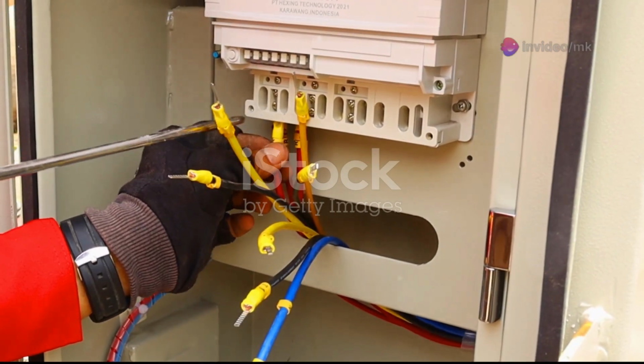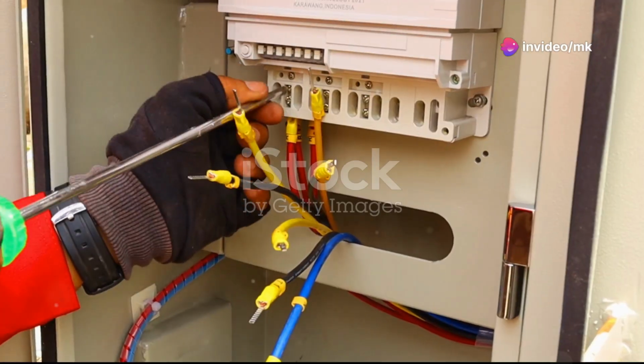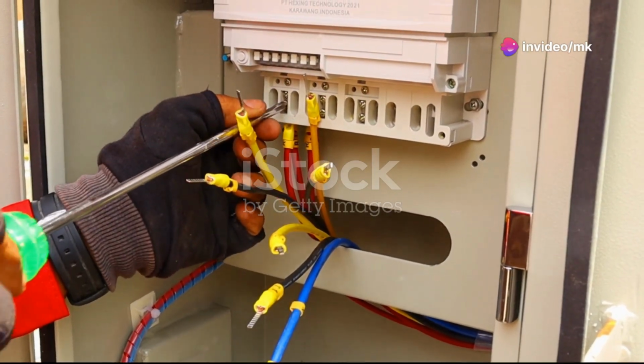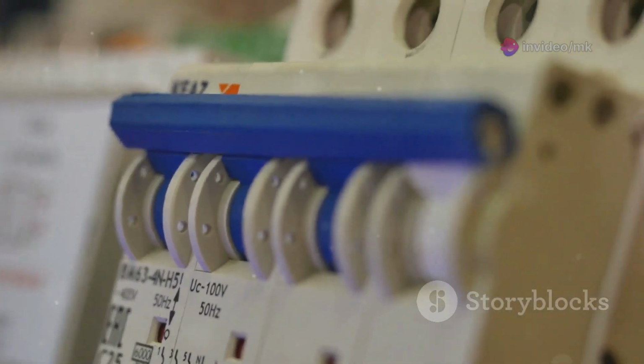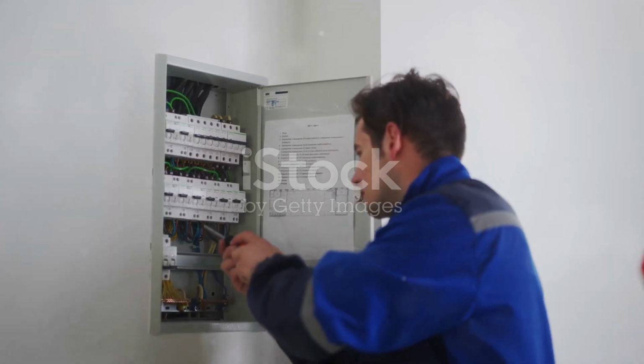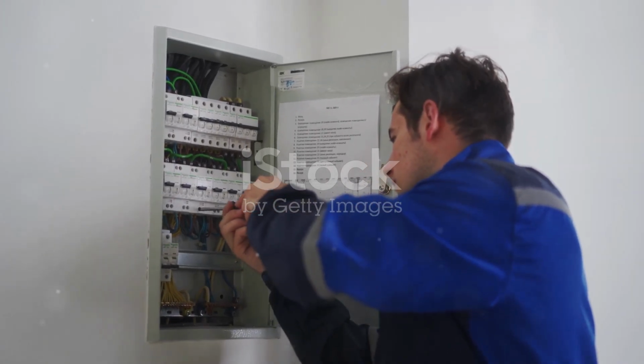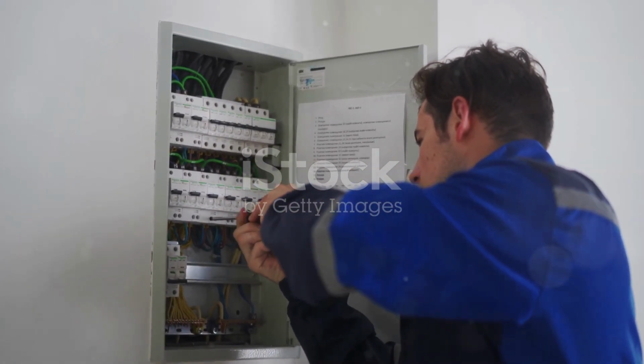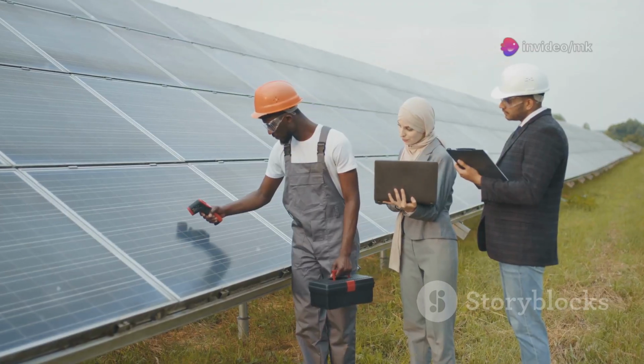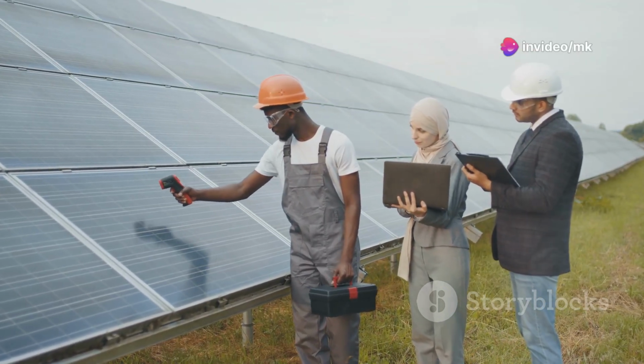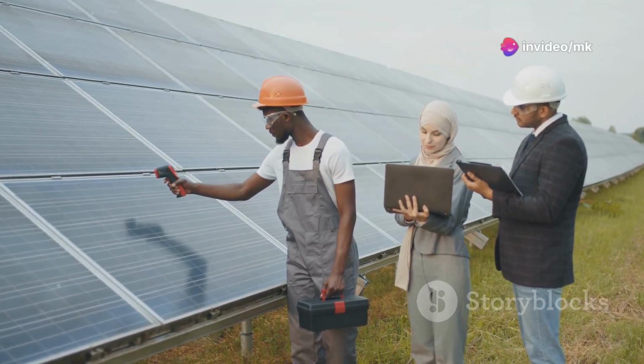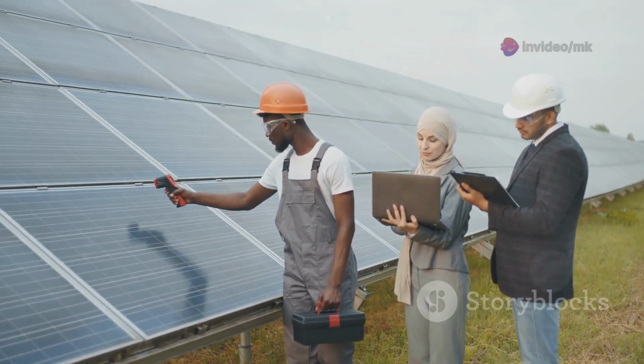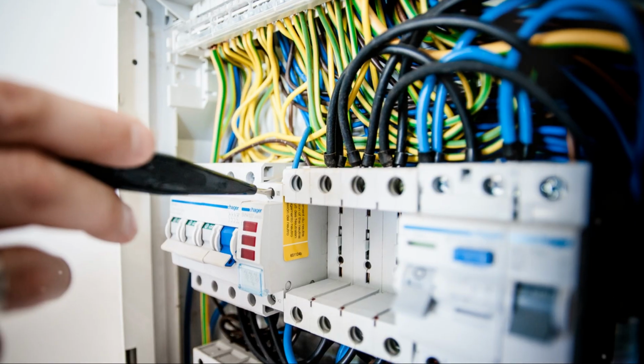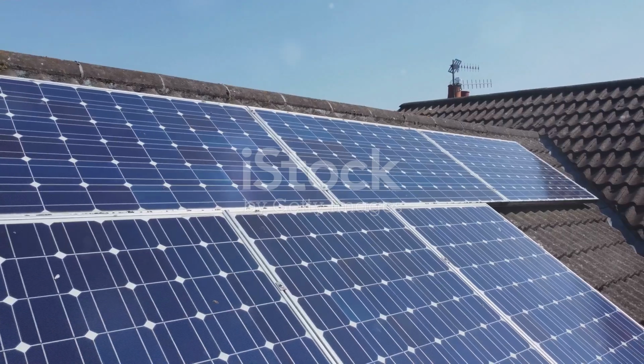On the AC side, the power your house actually uses, we need to protect the inverter's output and connect safely to your home and the grid. So, first up is the AC MCB for inverter output, which should be sized at 125% of the inverter's max AC output current. For example, 8,000 watts divided by 230 volts is about 35 amps, and then multiply by 1.25 to get around 44 amps. So a 50 amp breaker is the way to go.